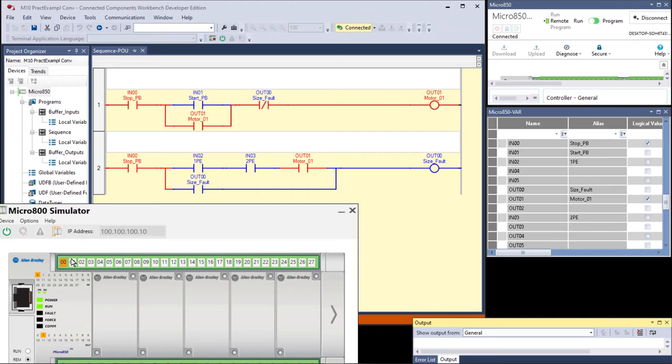Now, you can't tell by looking at this that there are any cartons approaching or on the conveyors. This is all that the PLC sees, that one PE and two PE, their optical paths are clear right this instant and on each scan. If we block the optical path of one PE as the carton passes through and clears one PE and then blocks two PE, then clears and passes on out of the conveyor, nothing happened.